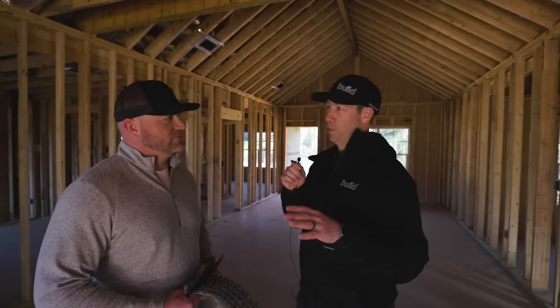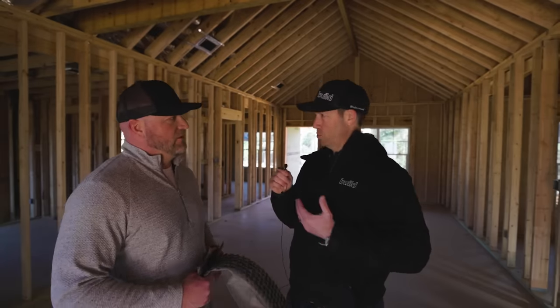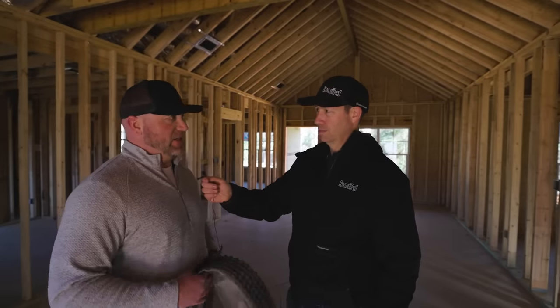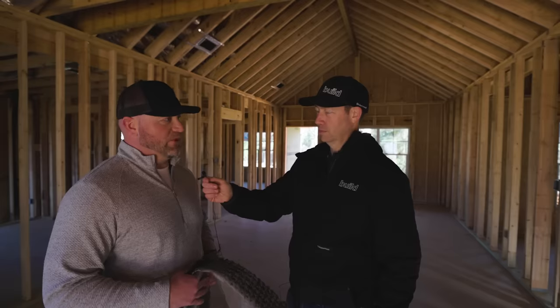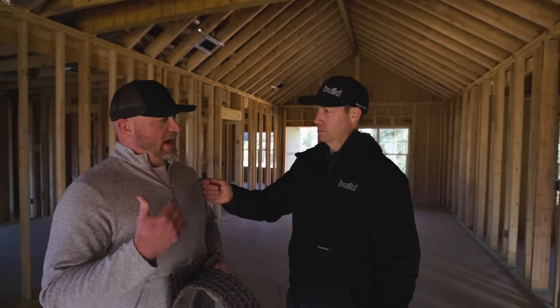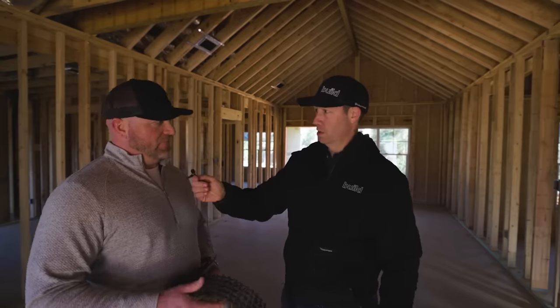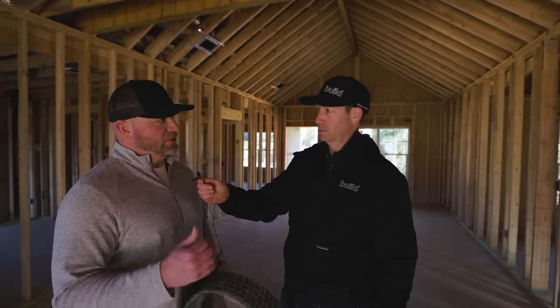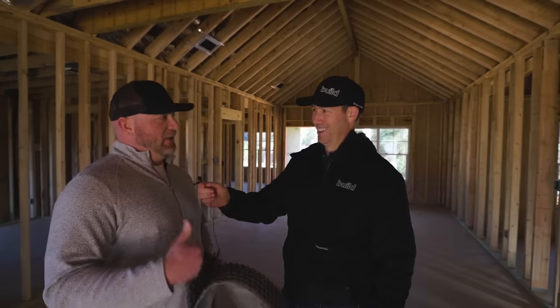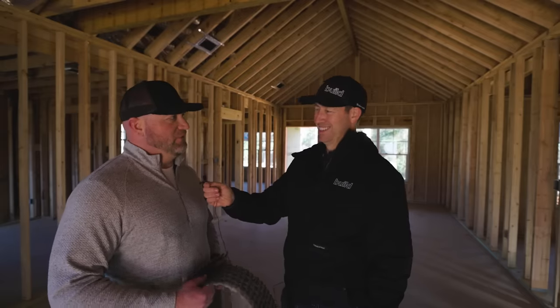So let's talk — the proof is in the pudding. What kind of numbers were you getting? Have you done any blower door tests? So the first two houses, pre-insulation, both blew a 3.7 ACH — code in Tyler is 3.0. After spray foam insulation, I blew a 1.1. Then two days later, Aero Barrier came out, and the end result was a 0.34 — both houses.